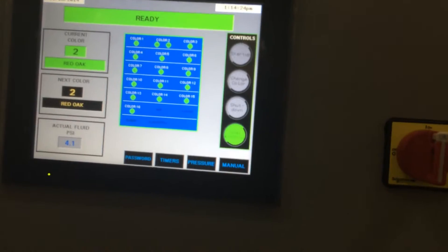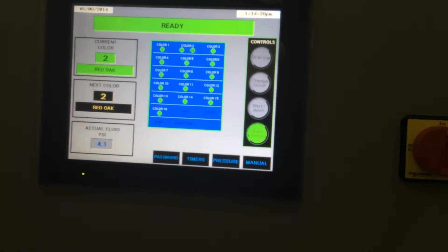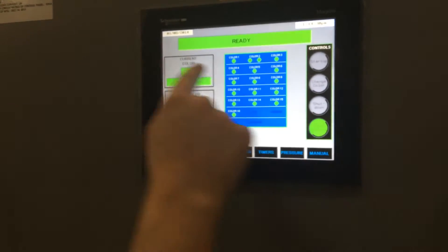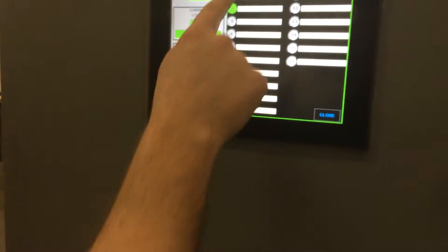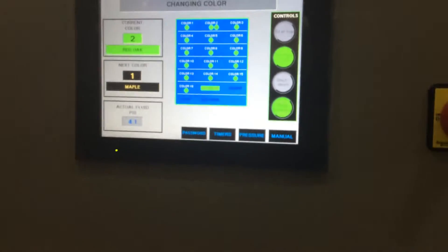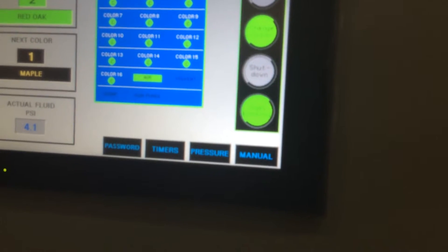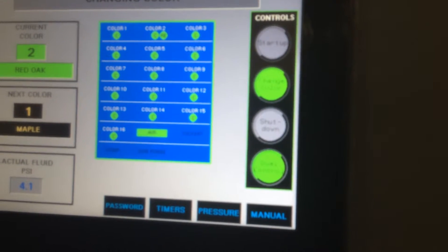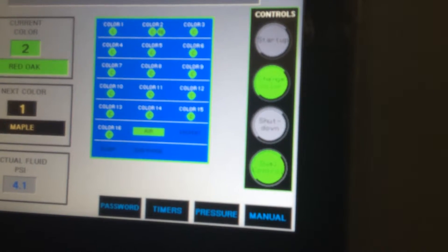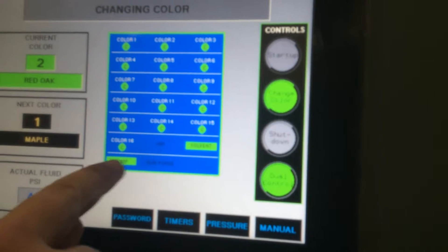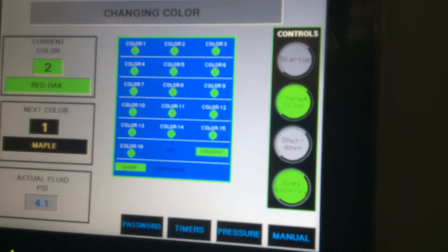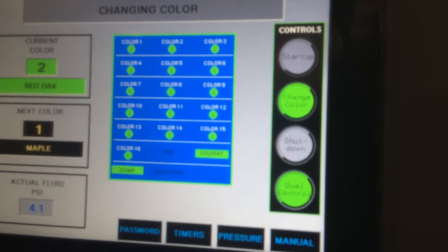To actuate a color change in the middle of the day or during production, simply select your color. We'll go in this case back to color one, close, and we'll actuate the color change. You can now see it's pushing air through color two and recovering all of the stain. It's now dumping the air. It's going to do an air solvent chop to scrub the lines through the guns and back out to the dump.